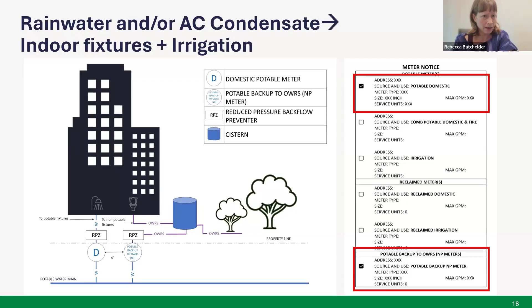You see these RPZs, and there's also color coding showing where the system uses purple pipe. We want to make sure that when installed, that pipe is purple and begins immediately downstream of the RPZ. Upstream of the backup meter, the water is potable, but as soon as you get on the other side of the RPZ, there's a potential that water could have on-site water mixed in, so we want it to be purple. That's this type of system, pretty straightforward.